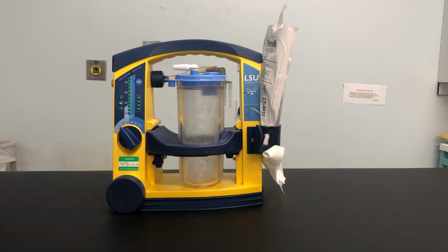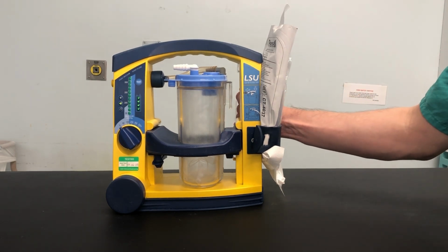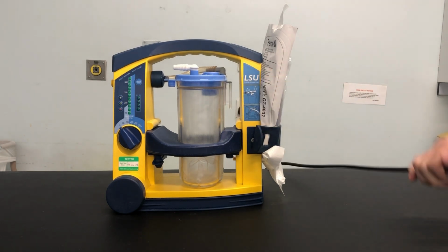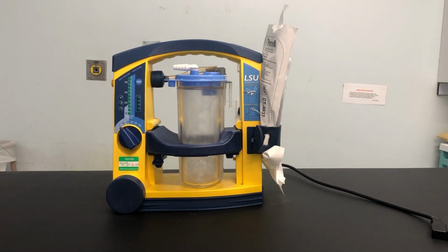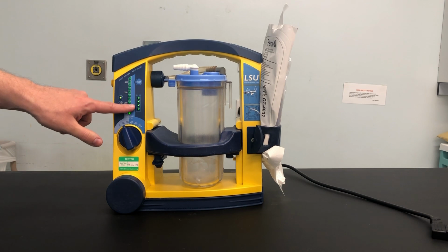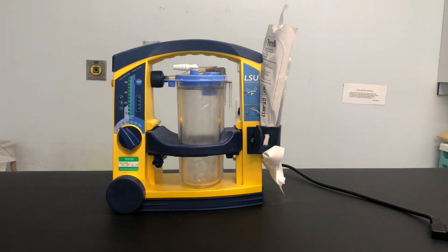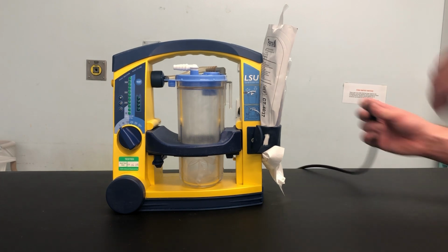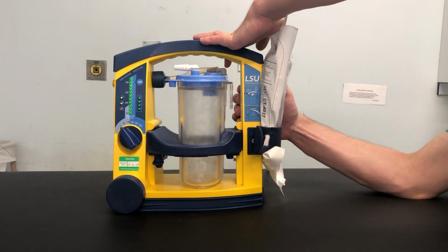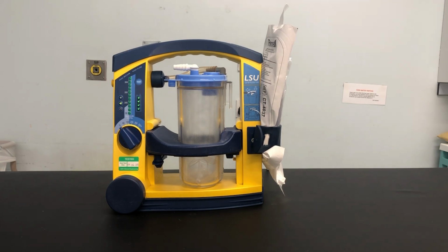How to perform the battery test. Immediately after turning the LSU on, and immediately after switching from external power operation to internal battery operation, all 4 LEDs flash for 5 seconds before the remaining battery capacity is displayed. Above 75% is 4 LEDs lit, 50 to 75% is 3 LEDs lit, 25 to 50% is 2 LEDs lit, and a little less than 25% is 1 LED lit. And battery low, about 2 minutes of operation left on 500 millimeters of mercury, is 1 LED flashing.